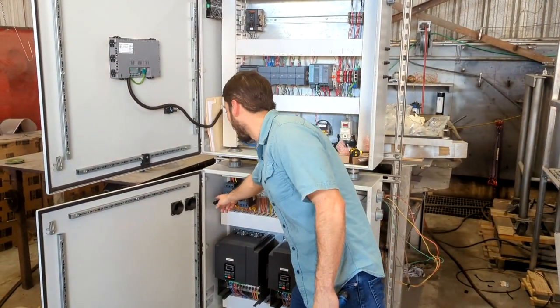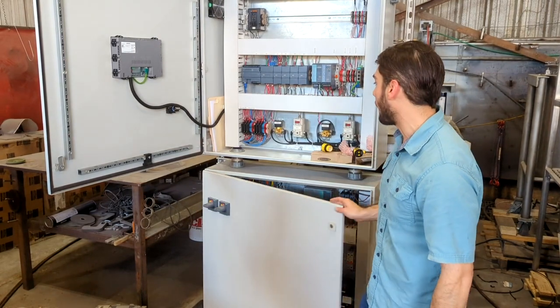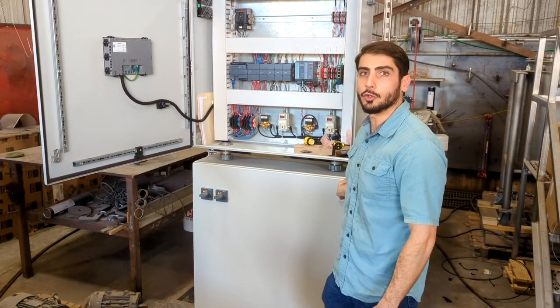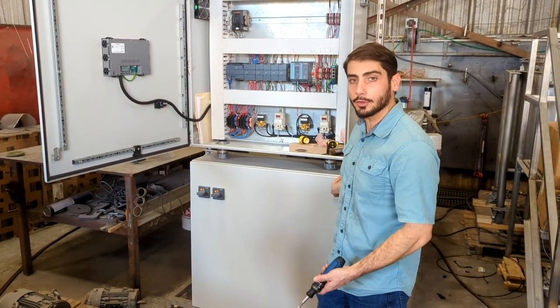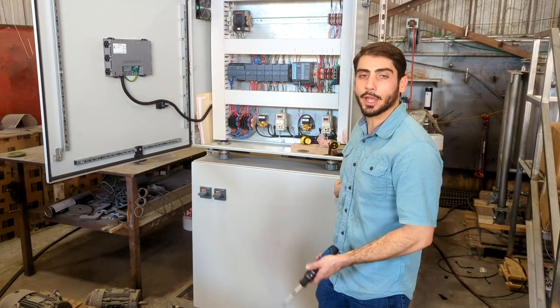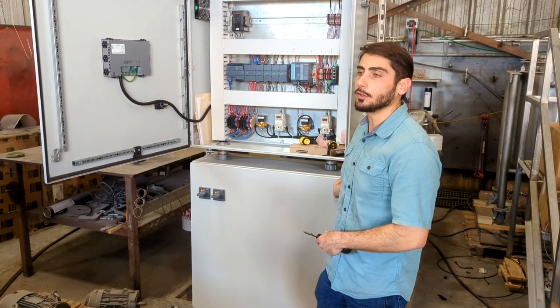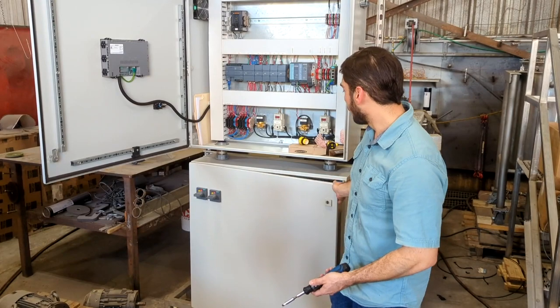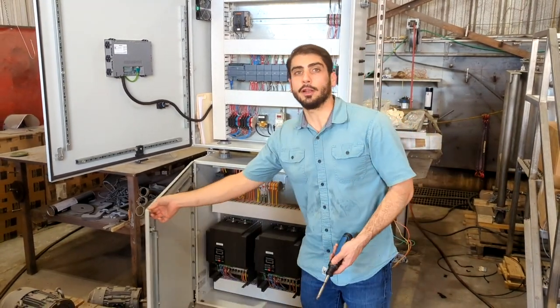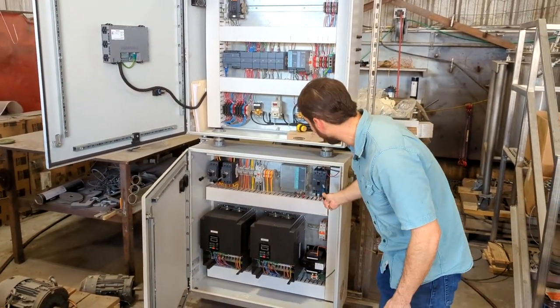We have these disconnects located on the outside of the panel for safety, so you can shut off the motor manually if you want to without having to go inside the panel, or your operators don't have to get exposed to the high voltage. This is a single circuit control panel. Everything links back to the main breaker here.